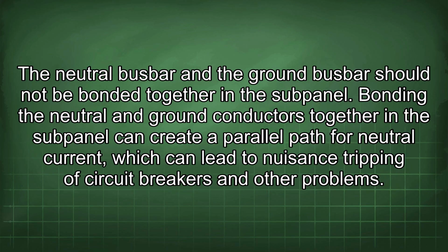The neutral busbar and the ground busbar should not be bonded together in the subpanel. Bonding the neutral and ground conductors together in the subpanel can create a parallel path for neutral current, which can lead to nuisance tripping of circuit breakers and other problems.